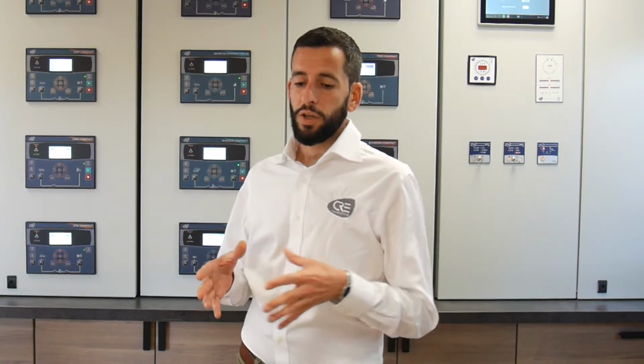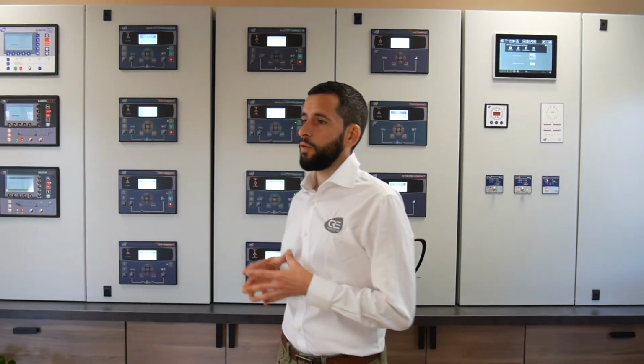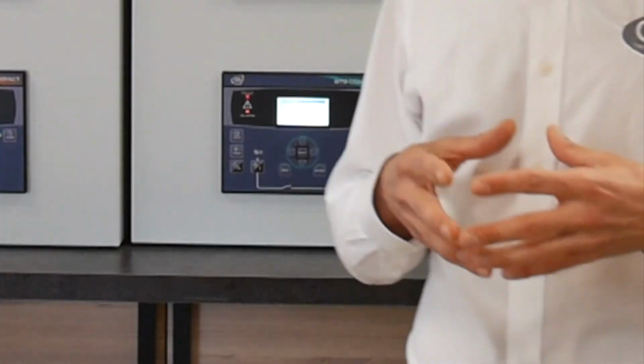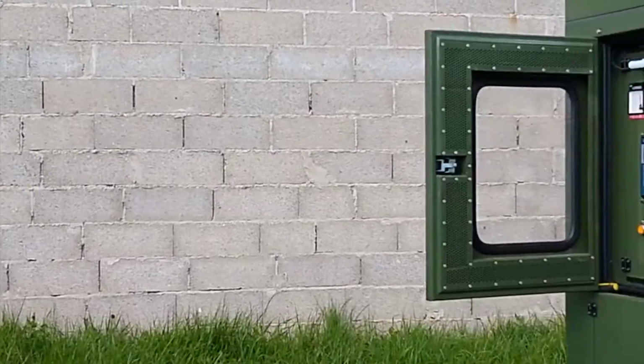Today we are going to explain to you how our new feature EasyCalib works. EasyCalib is a technical feature made for all paralleling applications, whether it's genset parallel with genset or genset parallel with mains. EasyCalib will assist you in the configuration of the analog output for speed control and the analog output for voltage control, which are the most complex and sensitive features to configure on an application today.